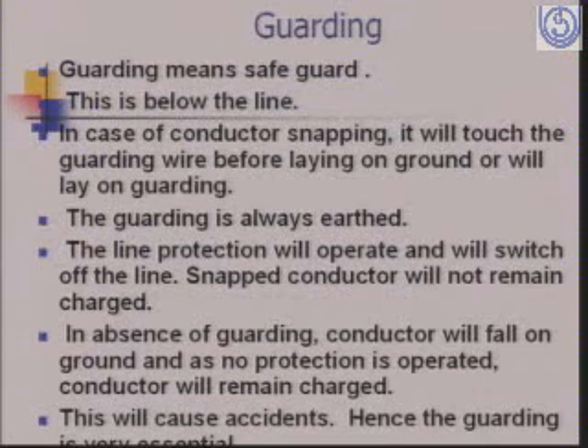Then we have guarding. Guarding means safeguard, as we all know. So this is below the line. In case of conductor snapping, it will touch the guarding wire before lying on the ground, or will lie on the guarding. The guarding is always earthed, and the line protection will operate and switch off the line. The basic idea is that once the conductor snaps, the conductor will fall on the guarding and the line protection will get operated. The snapped conductor will not remain charged. If it falls directly to the ground, then the snapped conductor will remain charged, and this will cause accidents.